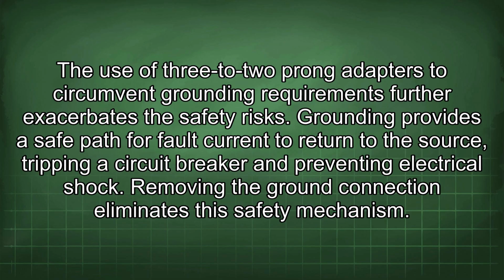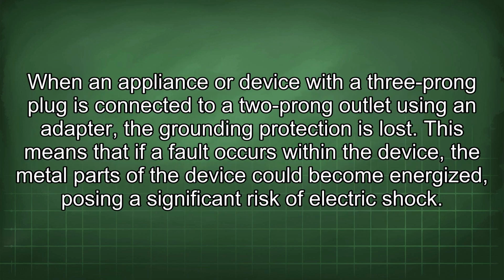The use of 3-to-2-prong adapters to circumvent grounding requirements further exacerbates the safety risks. Grounding provides a safe path for fault current to return to the source, tripping a circuit breaker and preventing electrical shock. Removing the ground connection eliminates the safety mechanism. When an appliance or device with a 3-prong plug is connected to a 2-prong outlet using an adapter, the grounding protection is lost. This means that if a fault occurs within the device, the metal parts of the device could become energized, posing a significant risk of electric shock.